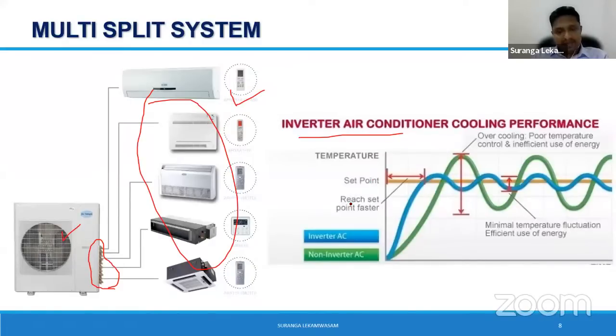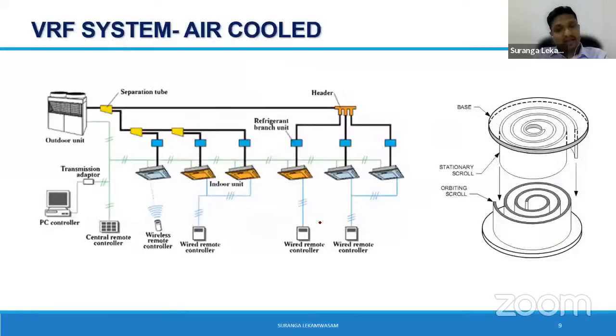There are negative sides as well, because some of the employers are specifying not to quote inverters, probably due to a very bad experience, because all these frequency controllers are actually power electronics. The circuit boards are located in the outdoor unit. So if you are living in a corrosive and polluted environment, the PCBs get issues. And if you want to replace that, probably one third of the cost you'll have to spend again. Therefore, some of the clients are not willing to go for inverter technology. But overall, especially in terms of energy, they are the best, right?